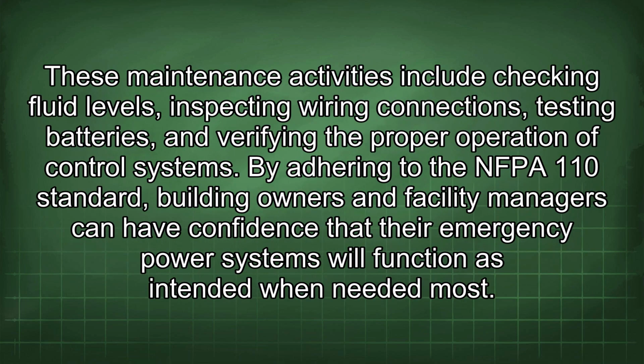These maintenance activities include checking fluid levels, inspecting wiring connections, testing batteries, and verifying the proper operation of control systems. By adhering to the NFPA 110 standard, building owners and facility managers can have confidence that their emergency power systems will function as intended when needed most.